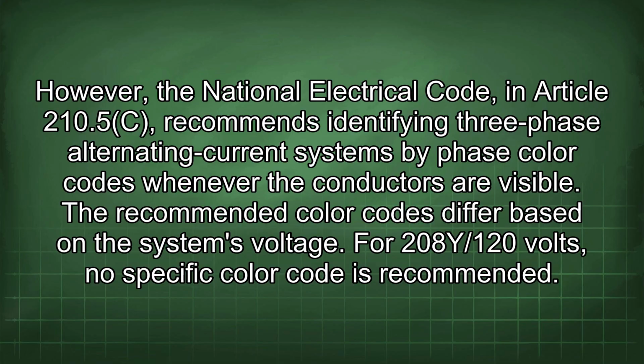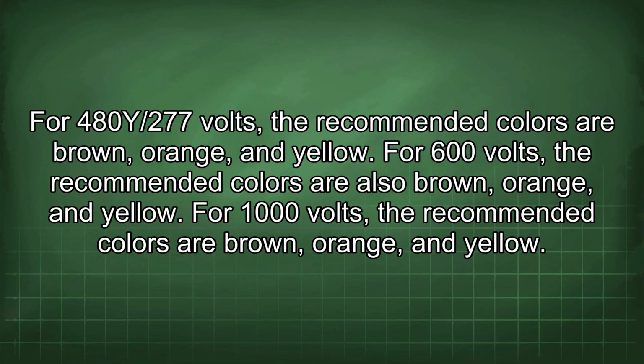For 208Y/120 volts, no specific color code is recommended. For 480Y/277 volts, the recommended colors are brown, orange, and yellow. For 600 volts, the recommended colors are also brown, orange, and yellow. For 1000 volts, the recommended colors are brown, orange, and yellow.